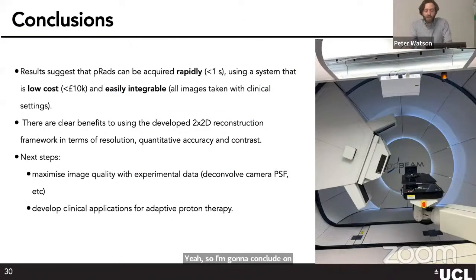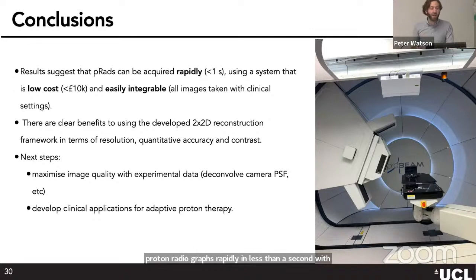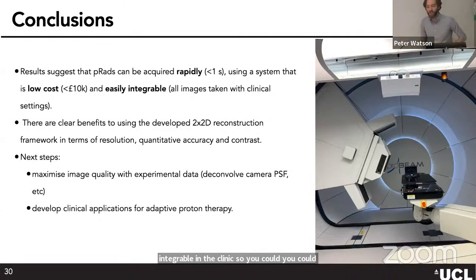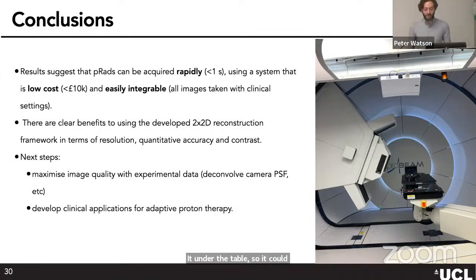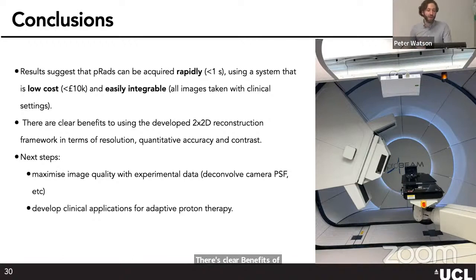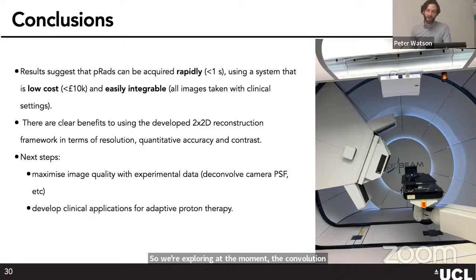In conclusion for proton imaging: we can acquire proton radiographs rapidly — in less than a second — with a mostly low-cost, easily integrable system that could be packaged on a small couch and slid under the treatment table. There are clear benefits to our reconstruction framework. Next steps include exploring deconvolution techniques to improve image quality and working on the clinical applications discussed earlier.